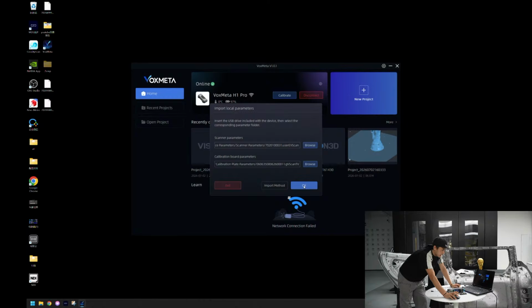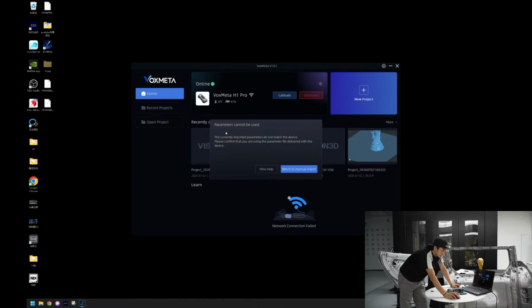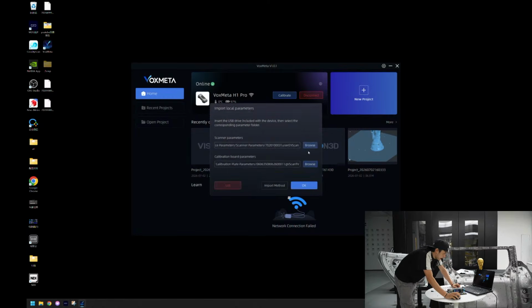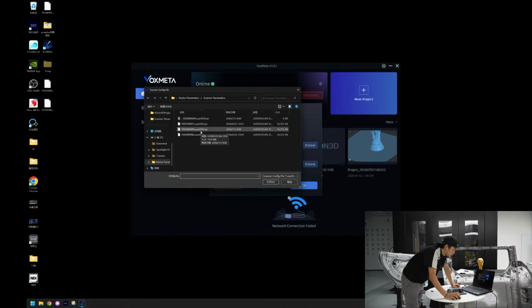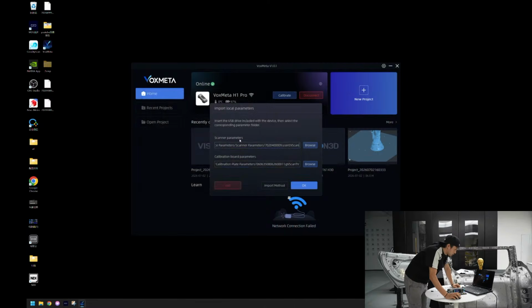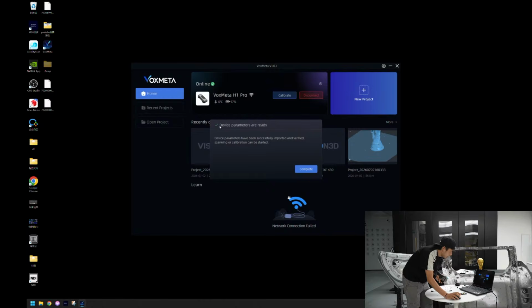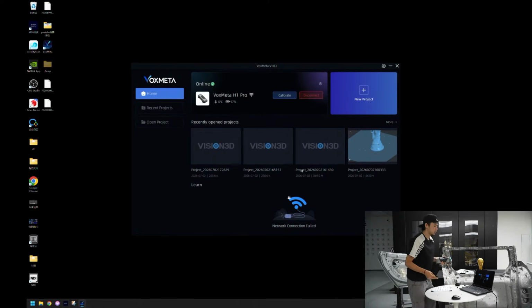That we put here and choose OK. You can see that it notifies us about the incorrect parameters. Parameters cannot be used. Currently imported parameters do not match the device, right? So we go and return to manual import, and we choose the correct one and see what the program will say to us. 009 is the correct one. We choose it. We chose the correct one for calibration board also. Now we can safely choose OK button. And you can see that device parameters are ready. So this was the whole process of importing the initial parameters and the configuration files of H1 Pro to your PC.